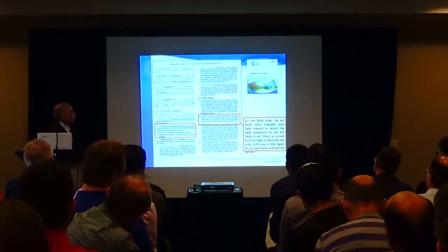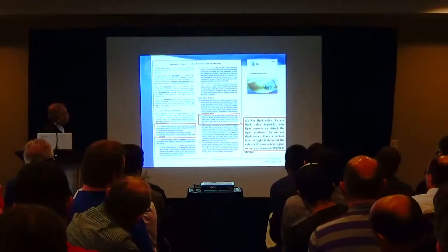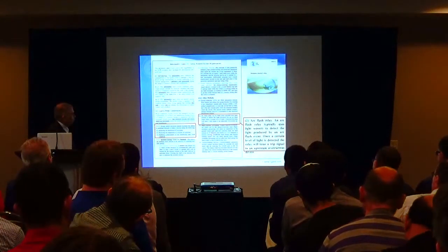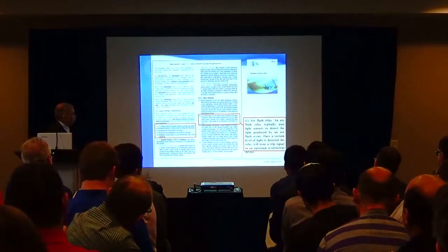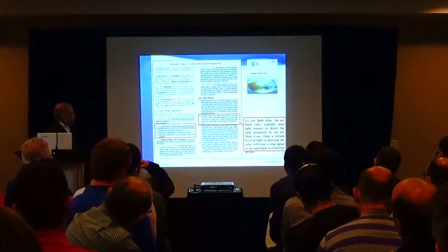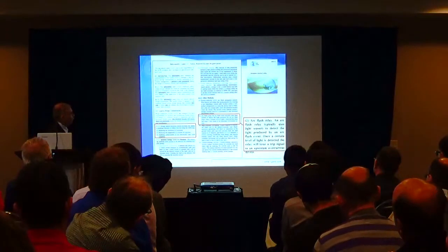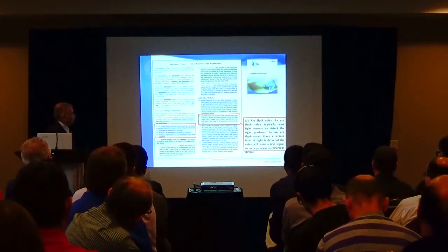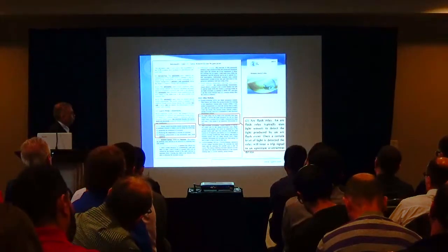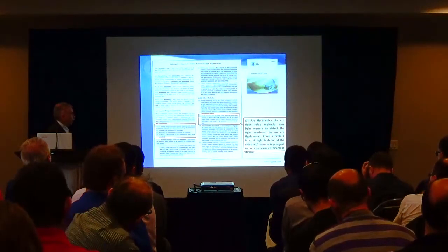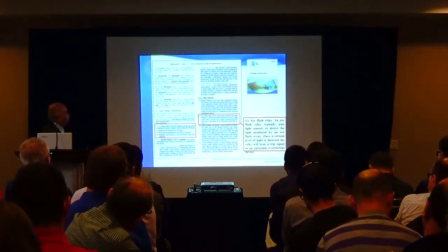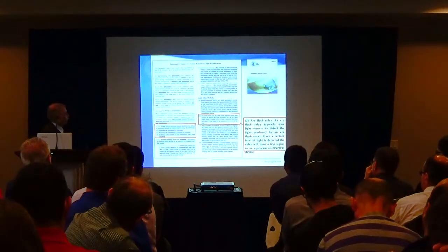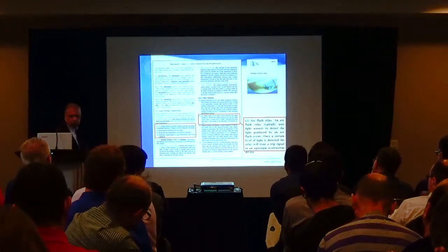So let's look at the document again and see where we are with this column of methods. So we took a look at the high resistance grounding in the previous, and now look at this two. The two says arc flash relay. An arc flash relay typically uses light sensors to detect the light produced by an arc. Once a certain level of light is detected, the relay will issue a trip signal to an upstream overcurrent device. So in the recommended methods, this figure says as item 2.